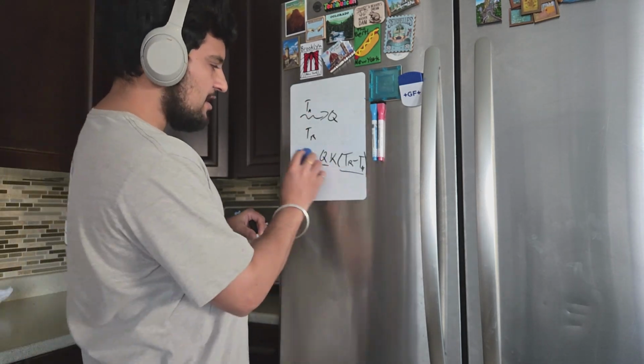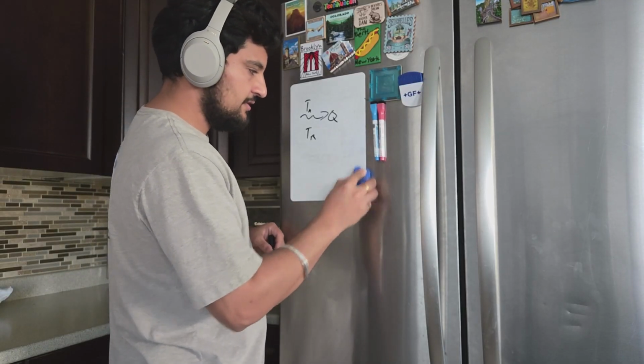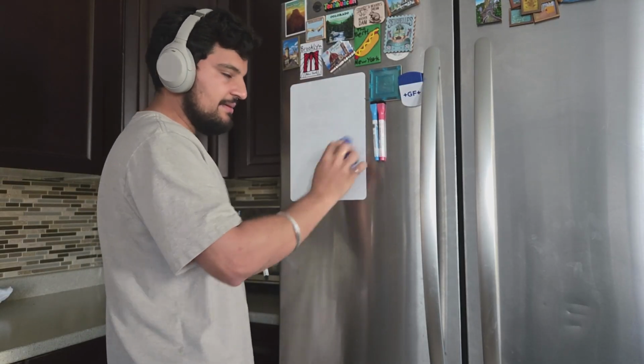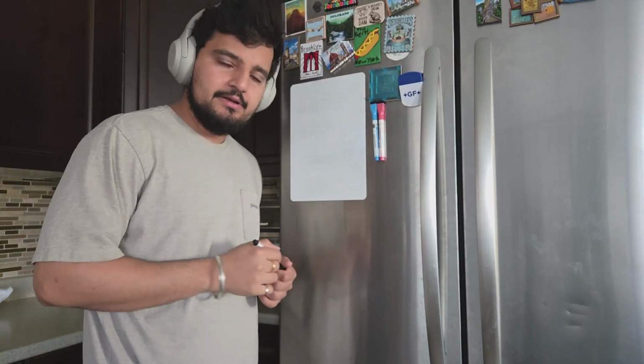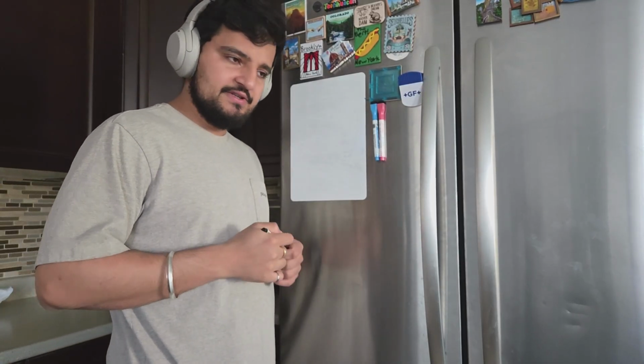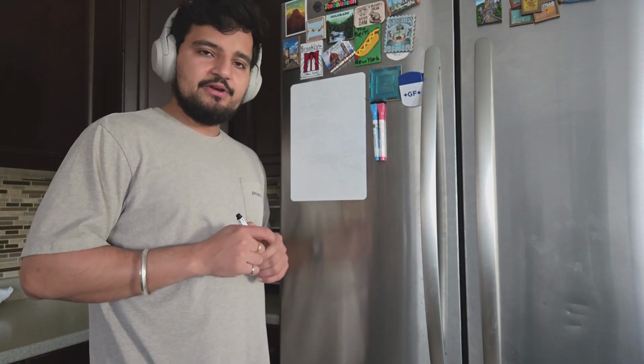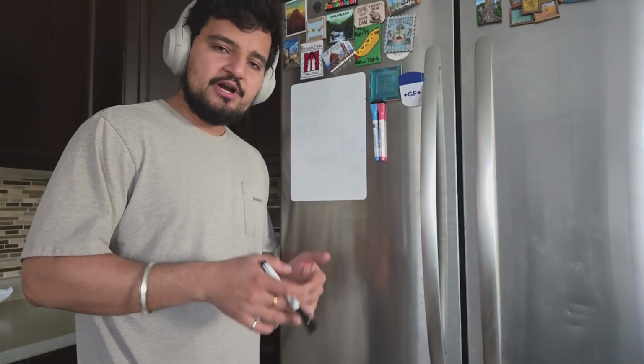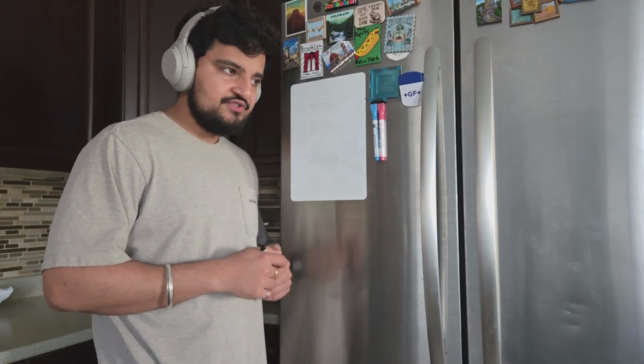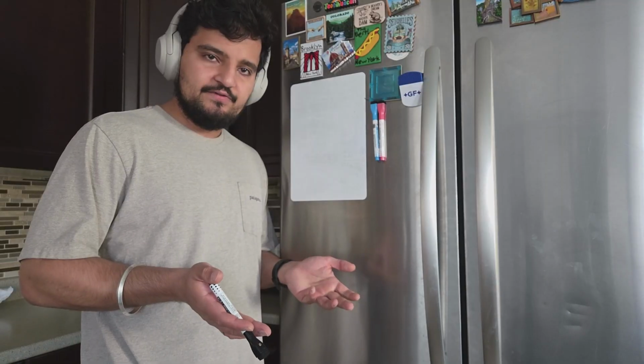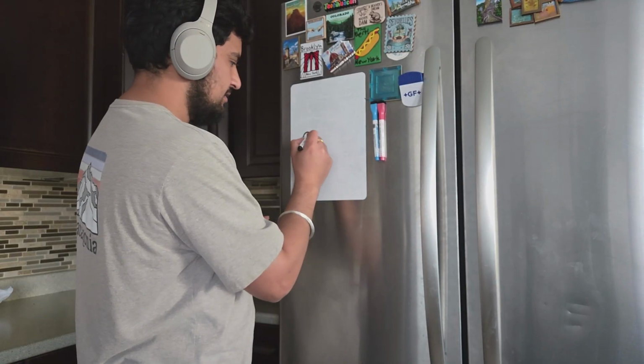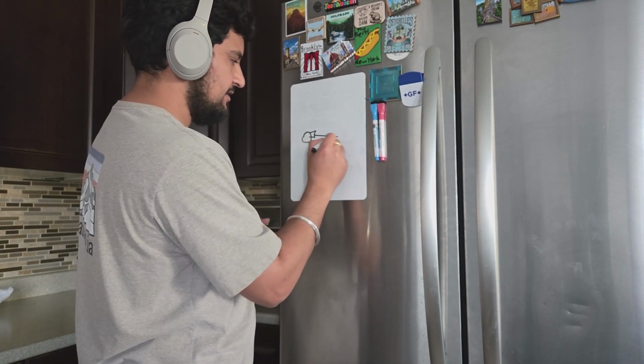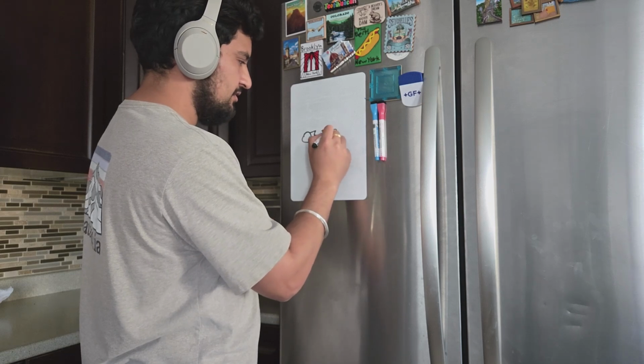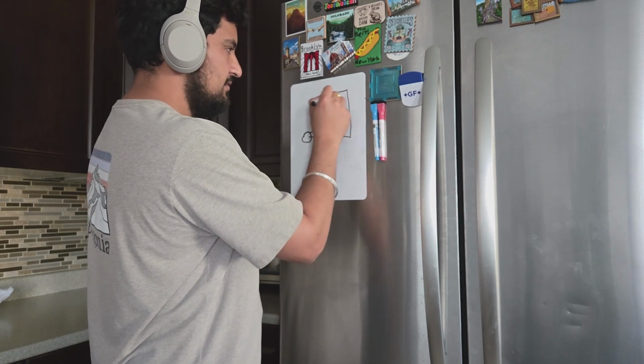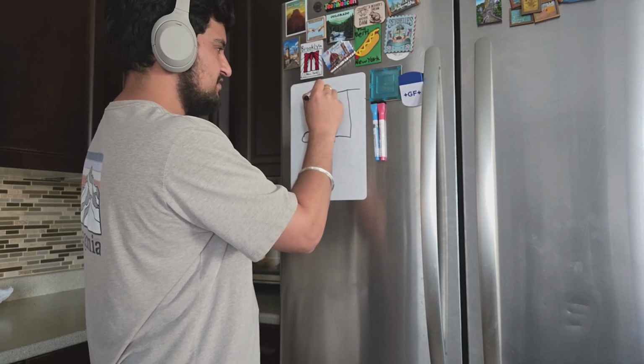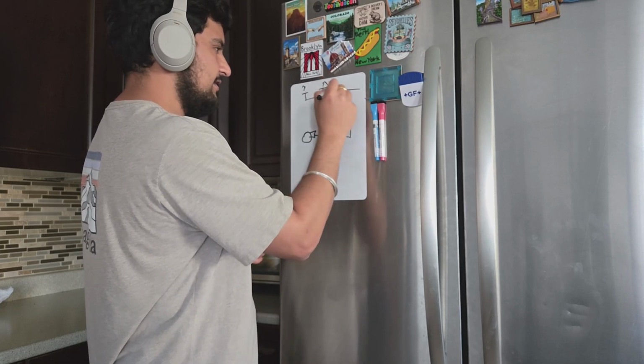So let's talk about why the airflow into your rooms might be lower than what's designed by the original designer of the house. Now, this is generally because there's higher than anticipated pressure loss through the duct system. And this could happen for a variety of reasons, right? So as we talked about, here's your fan pushing air, filter, cooling coil, ductwork, registers, right? So let's draw that diagram again.